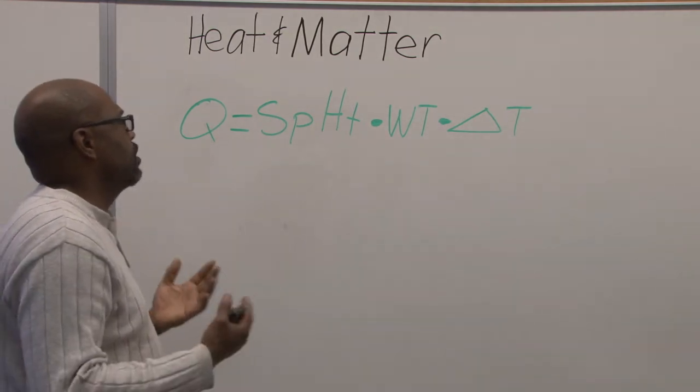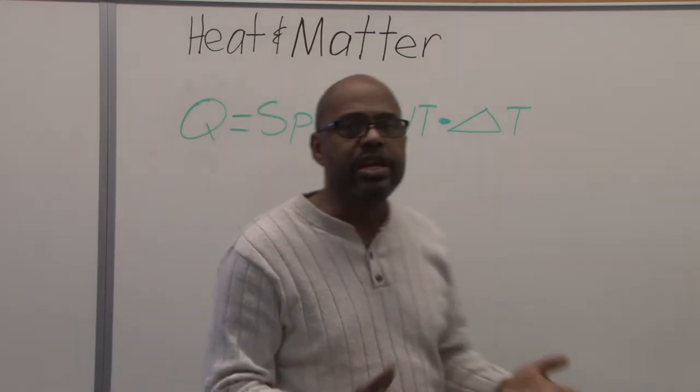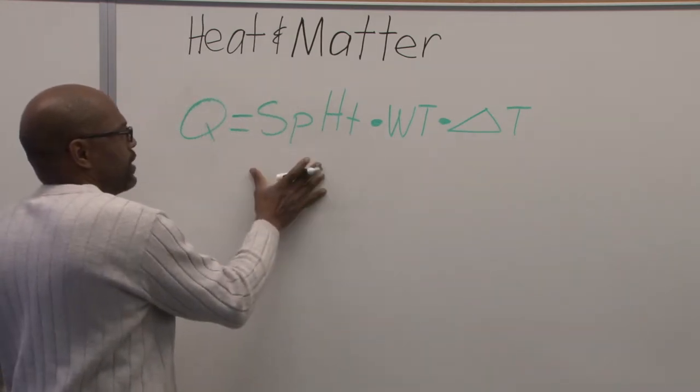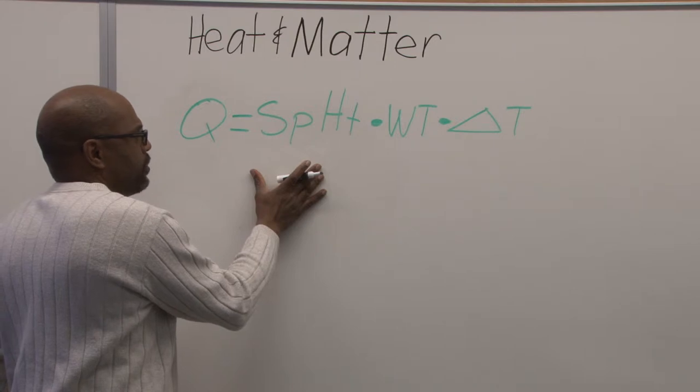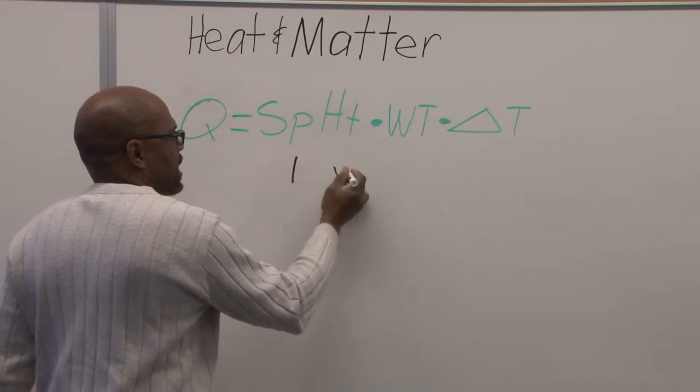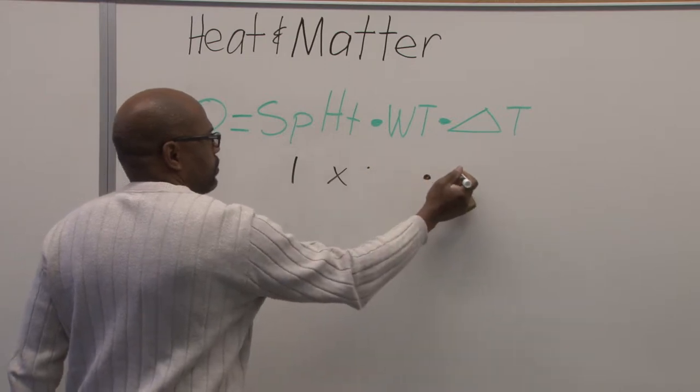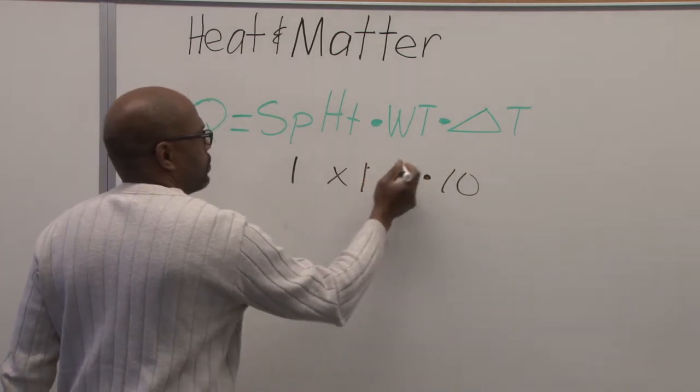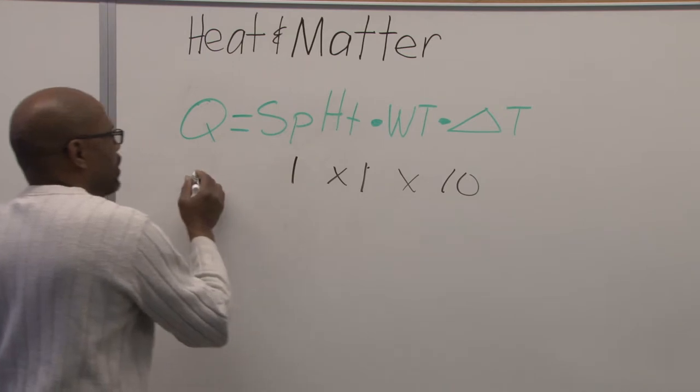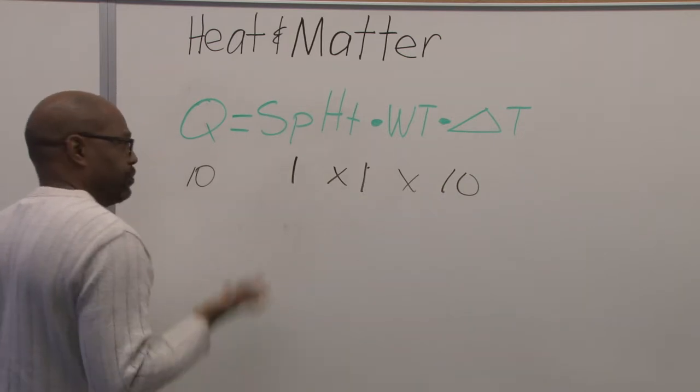So if we look at a substance and we want to measure it, it's very simple. We can take it and look at it and determine how much heat it would take. So if we look at, let's say, water, and we wanted to raise it ten degrees, and we had one pound of it. So the specific heat is one times ten degrees, and it's one pound. So it would take one times one times ten. So it would take ten BTUs to raise one pound of water ten degrees. Very simple.